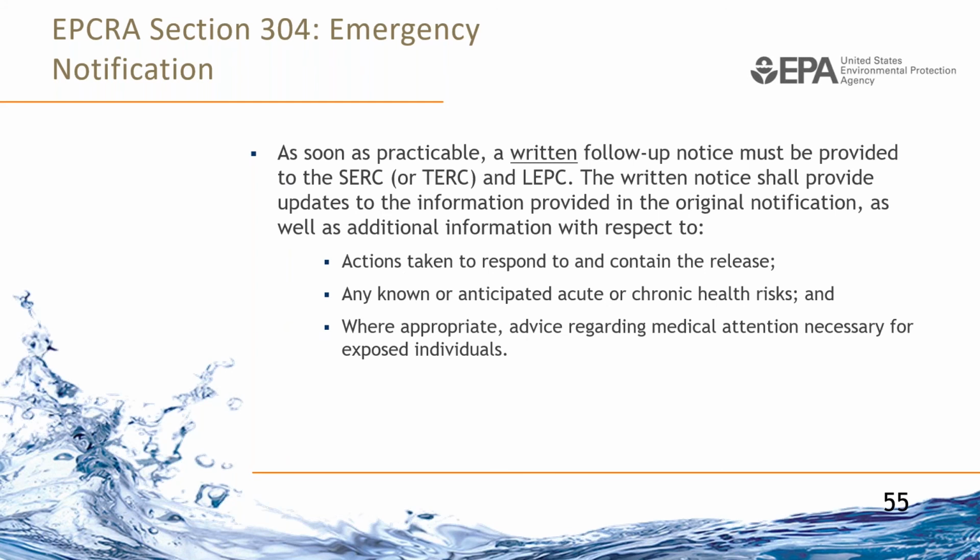So then, as soon as practicable, a written follow-up notice must be provided to the SERC or TERC and LEPC. The written notice needs to provide any updates that there have been to the information that we just went over on the previous slide, and additional information on what actions have been taken to respond to and contain the release, health risks, and if appropriate, advice on medical attention that's needed for people who are exposed. So, in summary, Section 304 requires an initial notification and a written follow-up after a spill by the facility to the SERC, TERC, and LEPC.